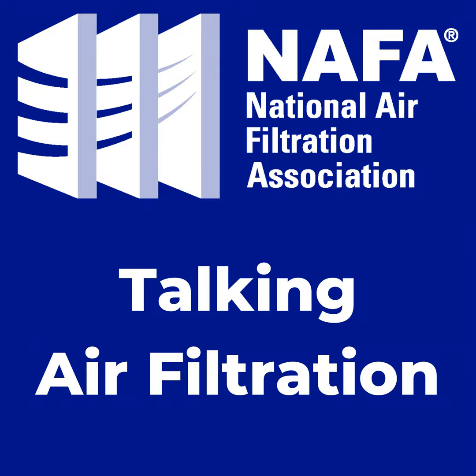When we had this feedback that we had seen some issues with the nanofiber coating, then we got better stuff back where you could see more nanofiber coating. This is an example of one where we saw some poor coverage, and then we had some feedback. And the one on the right, you see a really good nanofiber structure on there. So as we learn more about these processes and want to use these media, it's about making sure we have the right application of the nanofibers on the substrate.